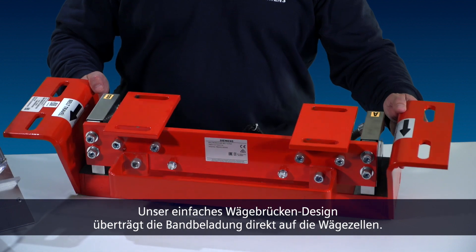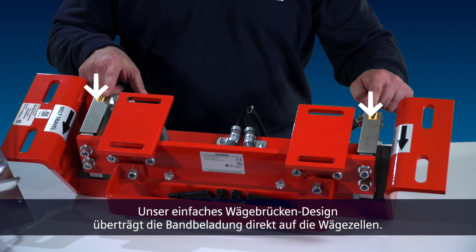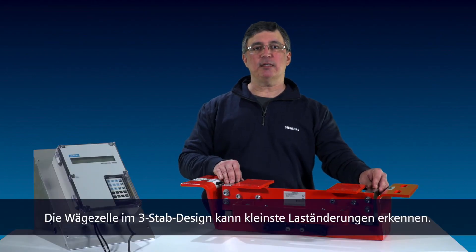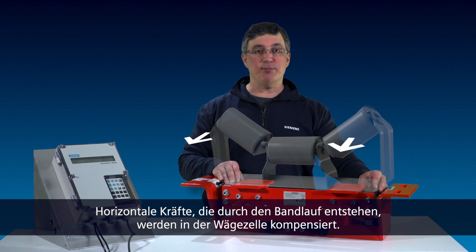What makes it so accurate? Let's take a closer look. Our simple weigh bridge design allows belt loading to be transferred directly to the load cell. The triple beam load cell can detect the smallest load change and makes it immune to horizontal forces created by the belt travel.